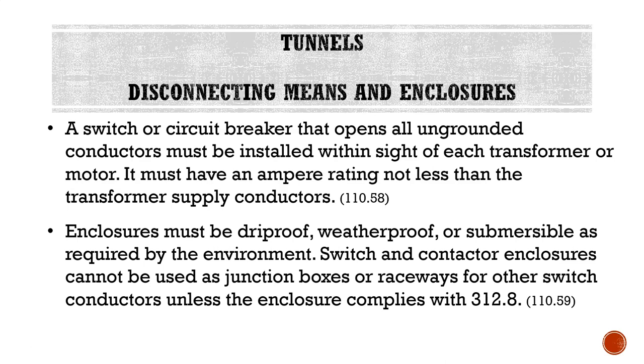Enclosures must be drip-proof, weatherproof, or submersible as required by the environment, and we would use table 110.28 — as discussed in our last lecture — to select an enclosure type that meets these requirements. Switch and contactor enclosures cannot be used as junction boxes or raceways for other switch conductors unless the enclosure complies with 312.8.